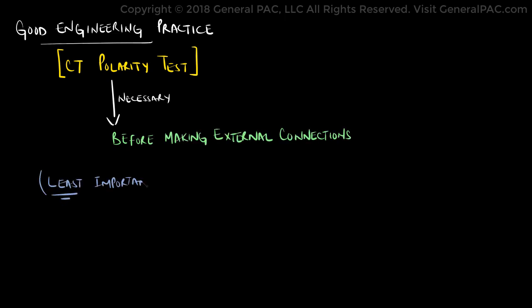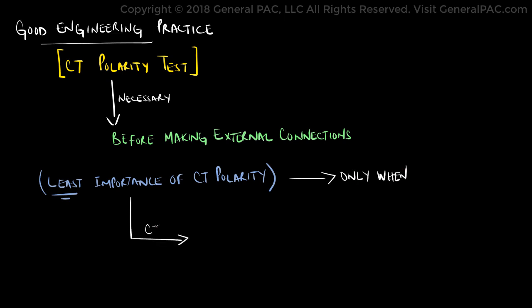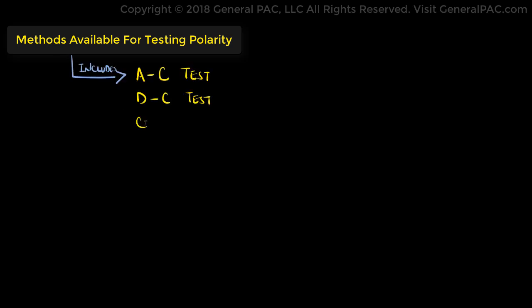The only case where CT polarity is of least concern to us is when we connect the CT to non-directional relays. There are various methods available to test a transformer's polarity. Some of the more common ones include the AC test, the DC test, the current method, and the phase angle method.